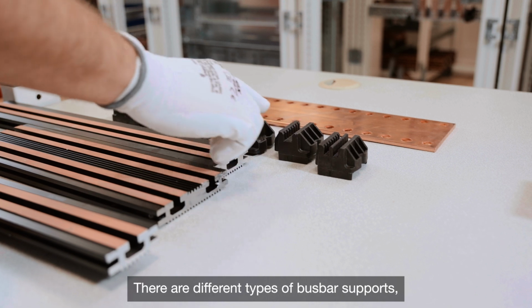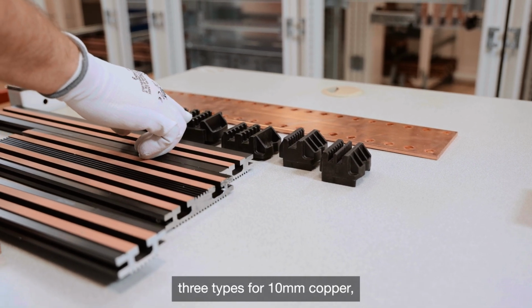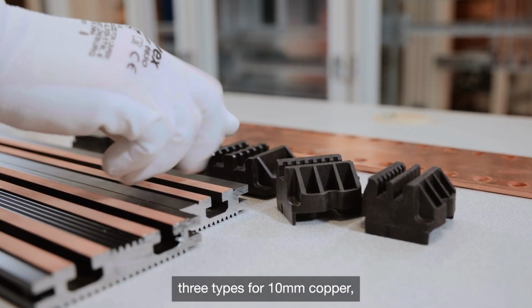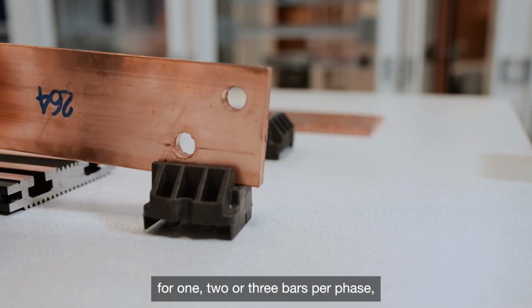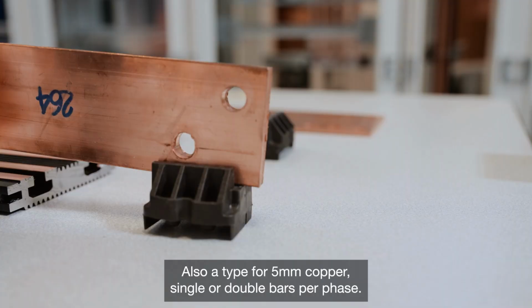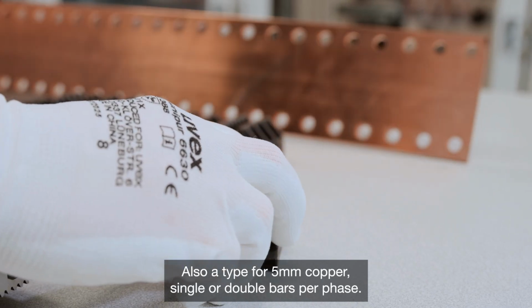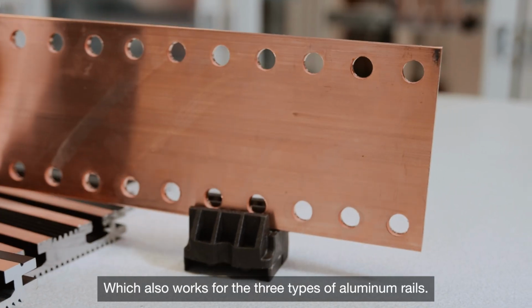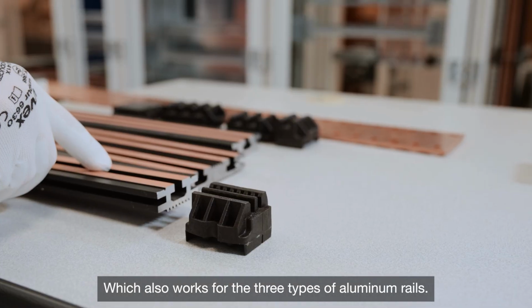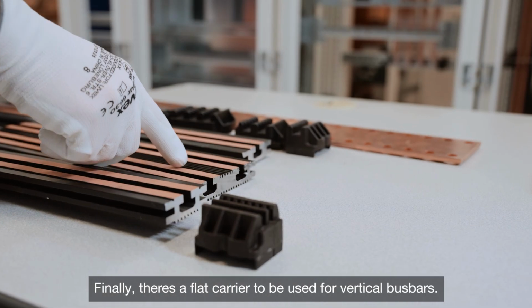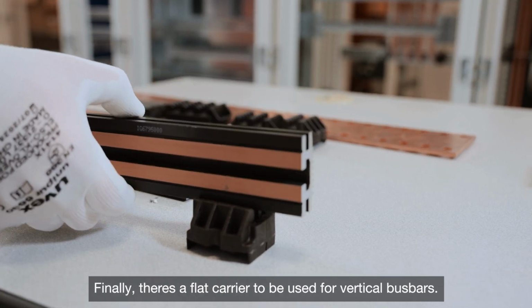There are different types of busbar supports. 3 types for 10 mm copper, for 1, 2, or 3 bars per phase. Also a type for 5 mm copper, single or double bars per phase, which also works for the 3 types of aluminum rails. Finally, there's a flat carrier to be used for vertical busbars.